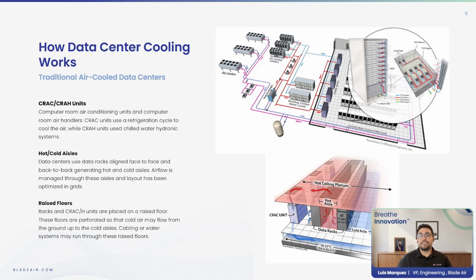Data centers also have racks spaced out in defined configurations, front to front and back to back. This configuration creates hot and cold aisles in optimized grids, maximizing airflow efficiency. They also generally have raised floors, perforated so cold air can travel through and up through the cold aisles and out through hot ceilings. It doesn't always have to be cold on the bottom and hot on top, but this is the general configuration since hot air rises naturally and denser cold air stays lower. The convenience of this layout is that water and cabling systems can run through the raised floors and hot ceilings to maximize both space and efficiency.